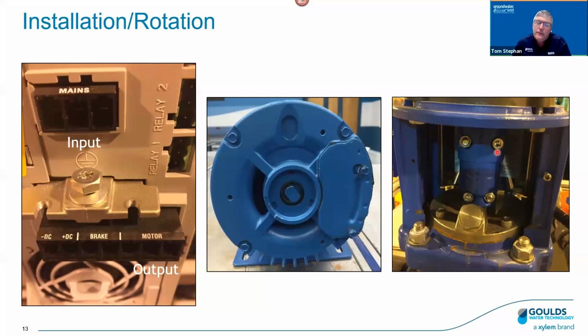On the right, we have an ESV. So an ESV is a multi-stage, normally vertical orientation, multi-stage, usually for a booster application. So in this case, I've got two arrows to look at. I've got one arrow on the pump body. And if I take the coupling cover off, and again, we're just going to bump it just to check for rotation. We can see that that coupling also has an arrow on it. We can see the rotation. So we can check rotation there.